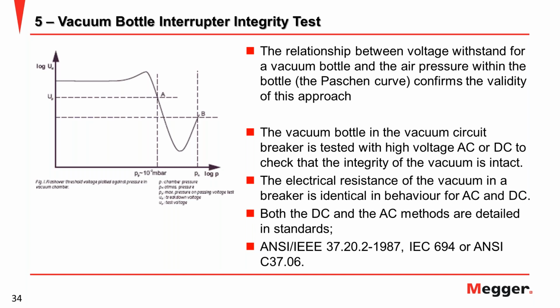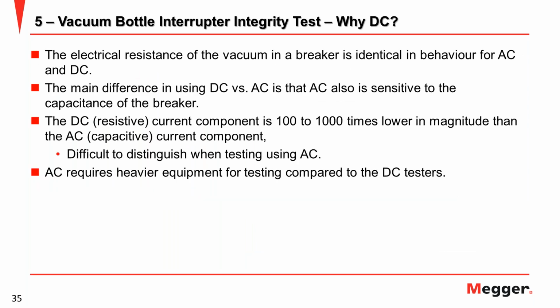This is why you can see for the vacuum bottle test, almost all testers provide DC output rather than the AC output. The reason is that the DC resistive current component is 100 to 1000 times lower in magnitude than the AC capacitive current component. So this is the reason why most equipment testers provide DC.